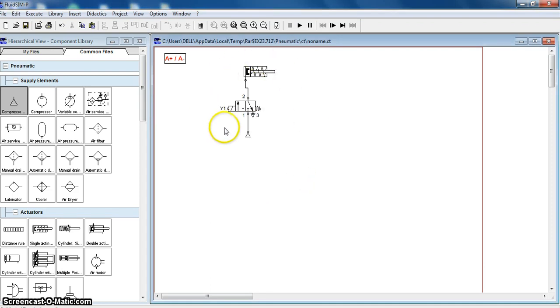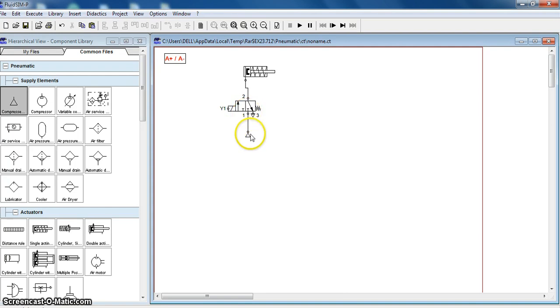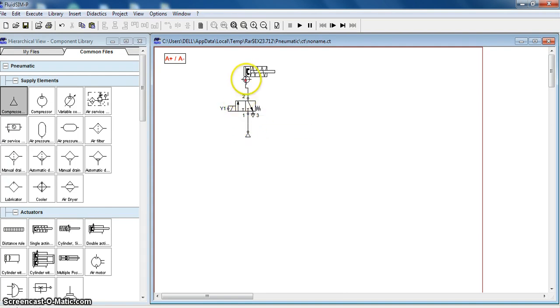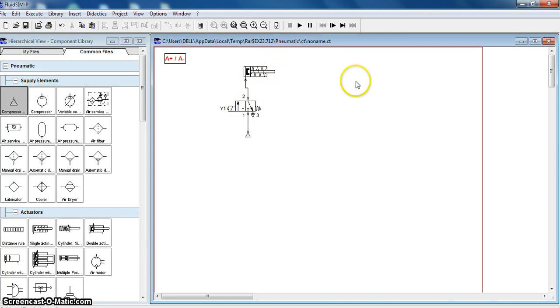This is the pneumatic circuit. When solenoid Y1 gets charged, this valve will switch over. As the valve switches over, this position will come here, and the supply from the compressor will go from here to here, and from here to the cap end of the cylinder. And the cylinder will extend.